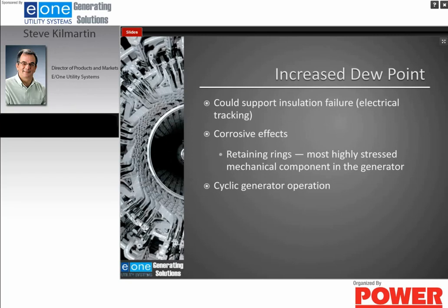So one of the reasons you want to keep your dew point low is because of insulation failure, and also because of the corrosive effects that increased moisture could have, particularly on the retaining ring. The retaining rings are the most highly stressed mechanical component in the generator, so you want to make sure that they keep their integrity. Years back, the retaining rings were built with 18-5 stainless steel. 18-5 stainless steel was susceptible to moisture, causing cracks in the ring, causing it to fail. Rings nowadays are made with, I believe, 18-18 stainless, and it's a far better stainless. However, you still don't want moisture in your generator, and moisture can still have an effect on 18-18 rings.